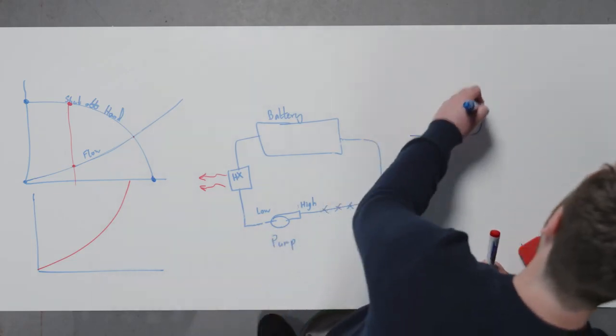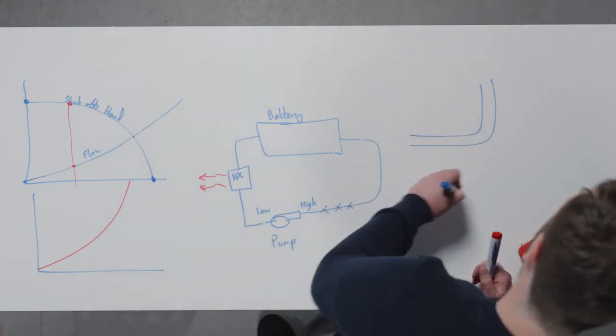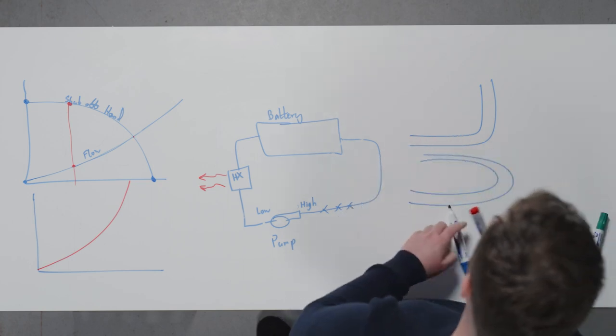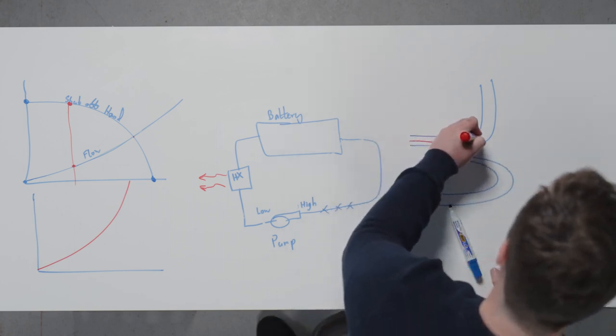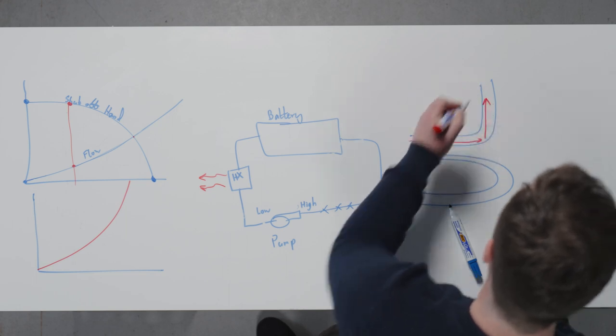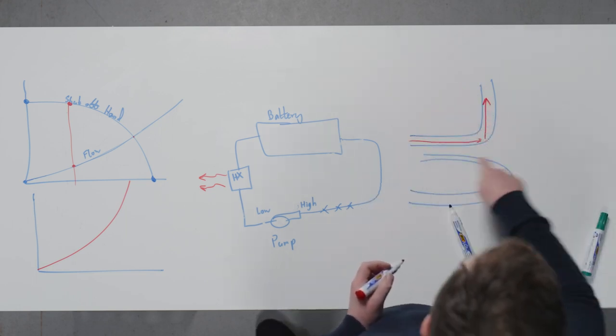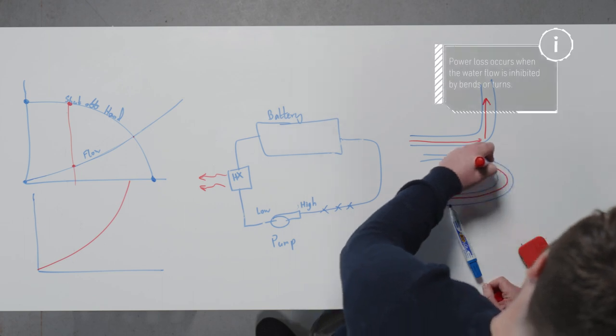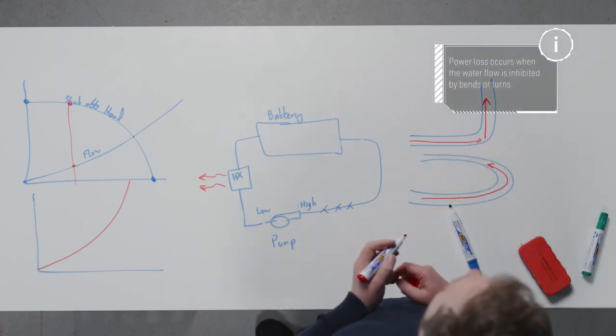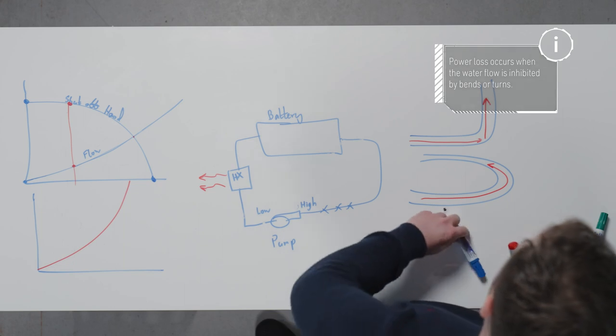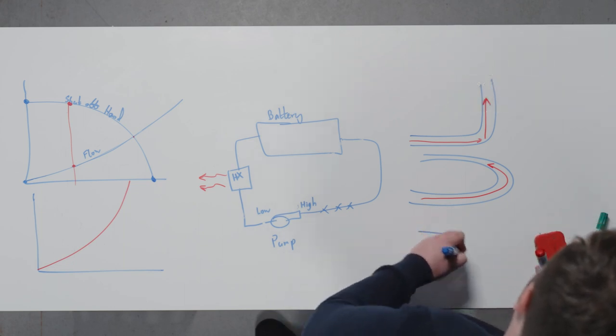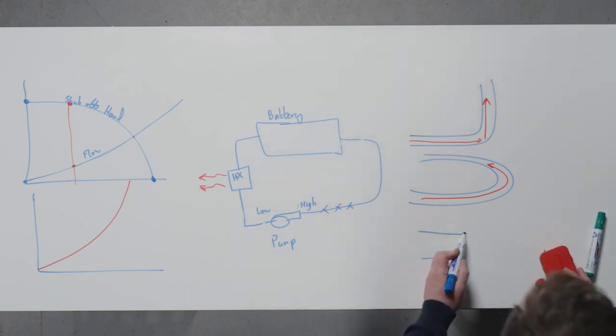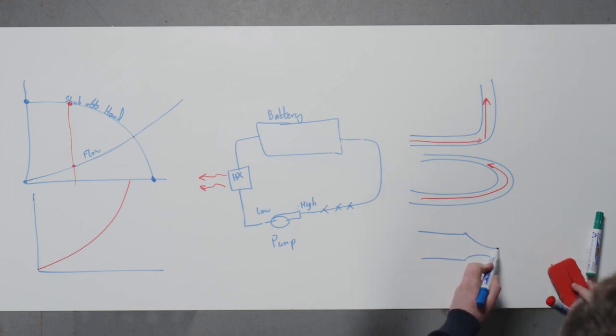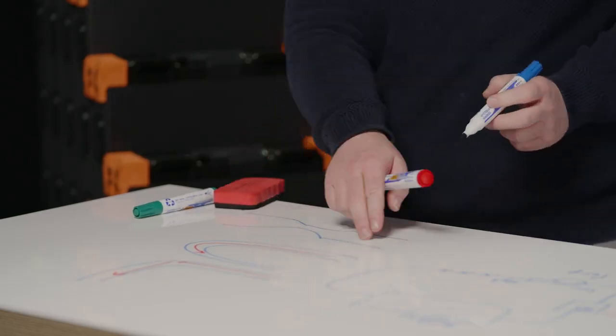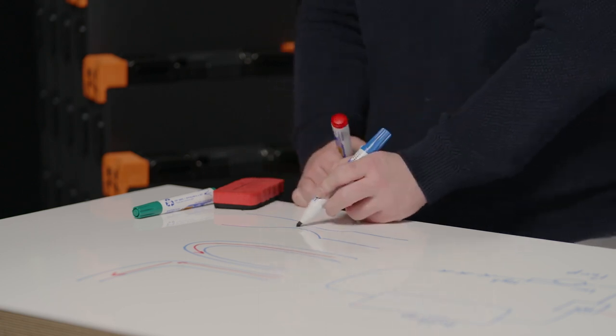So basically, if you've got a bend or a loop back in a system, the water is flowing here and then it's having to change direction. There's loss in the system when it has to change direction, and the loss is maximized when it has to turn around and come back on itself. Also, you can get pressure drop when there's a change in velocity of the flow. So if you've got a restriction in a pipe and the water has to increase speed to get through this constriction, that will also lead to pressure drop.